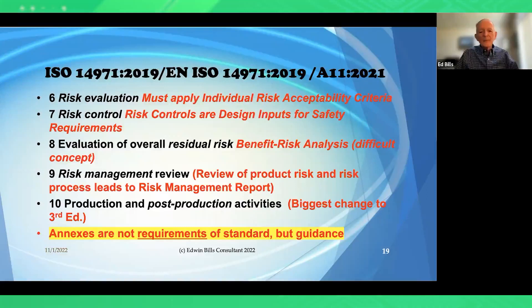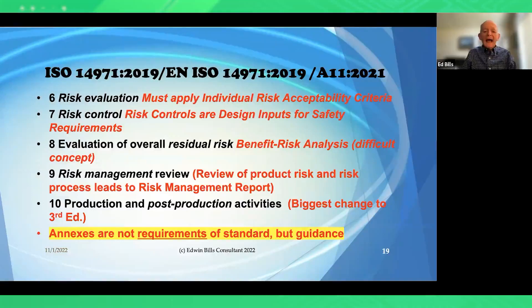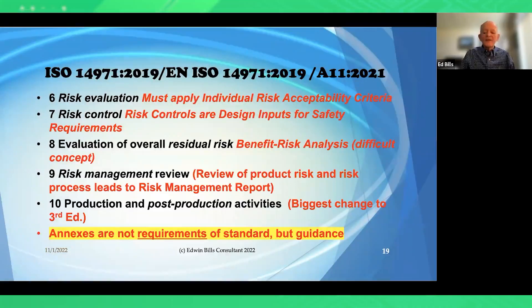Clause eight covers evaluation of overall residual risk and benefit-to-risk analysis — a difficult concept. The FDA has done the best job in their guidance documents, with four guidance documents on benefit-to-risk. ISO TR 24971-2020 also has good information. Clause 10 is the biggest change in the 2019 edition: you can no longer wait for the phone to ring on complaints. You must actively go out and look for information related to the performance of your product — searching the internet, looking at clinical literature, and monitoring various channels.